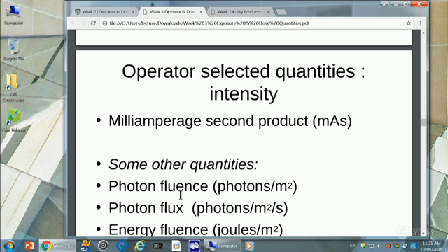Some people, when they're talking about exposures and how much radiation the person's getting, as this lady told me at halftime, sometimes multiply the kVp and mAs to give you a number. Okay, you can see how rough that is. You're using kVp and you're using mAs, which the manufacturers have fiddled with. So it's some indication, but it's not a very valuable one.